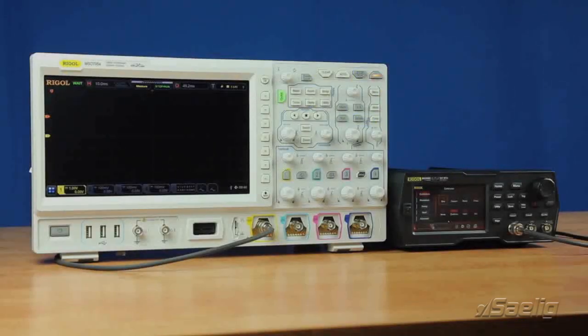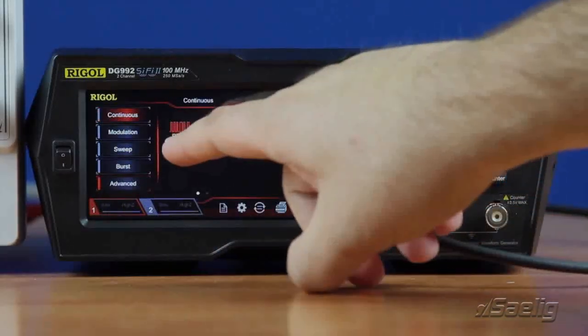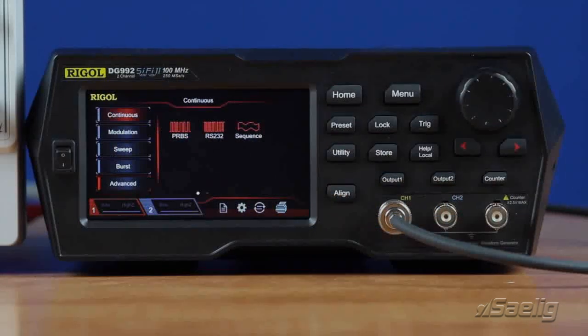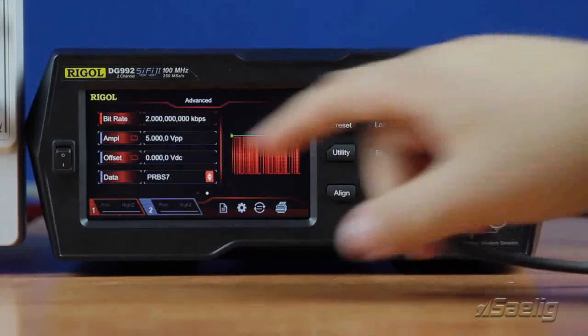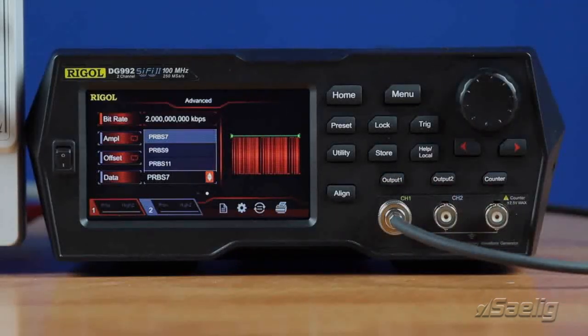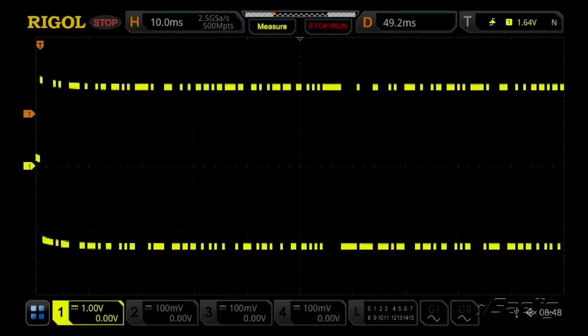One of the three advanced functions of the DG800 and DG900 series arbitrary waveform generator is pseudorandom bitstream. To find this function, you go into the advanced menu of the instrument and then hit the PRBS function, which stands for pseudorandom bitstream. Within here, you can choose your baud rate, amplitude, offset, and your data choice — PRBS7, PRBS9, or PRBS11. Once you've selected all those settings, you turn on the output and it will create a pseudorandom bitstream, which is great for testing circuitry and filter testing before you actually send data through your circuitry.